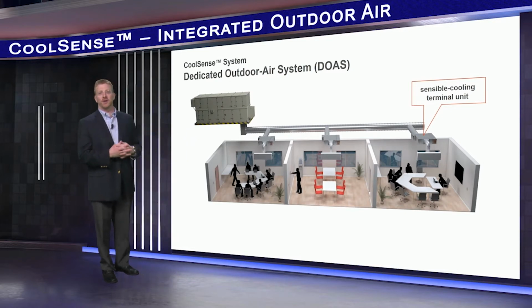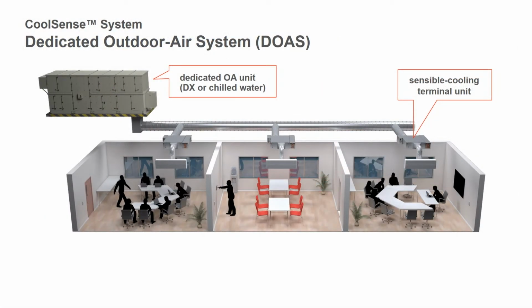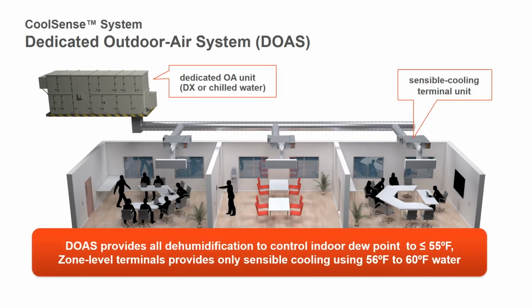Here, each zone is served by a terminal unit equipped with a variable speed or ECM fan and a sensible only chilled water cooling coil. And here, a dedicated outdoor air system provides all the dehumidification needed to keep the spaces below a desired dew point. Then, the chilled water supplied to the zone-level terminals is controlled to a temperature that is warmer than the space dew point. Typically, the indoor dew point will be 55 degrees, and the chilled water temperature will be a couple degrees warmer, typically between 56 and 60 degrees, to ensure that the terminal units operate dry.